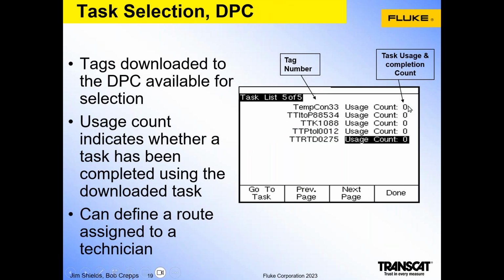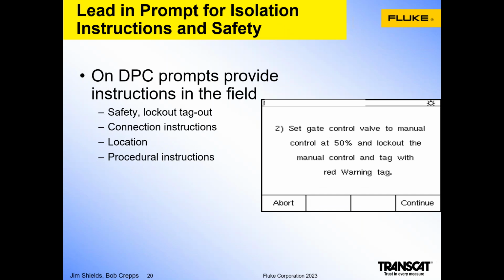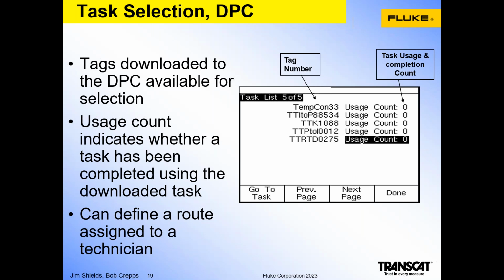When tags are downloaded to the Documenting Process Calibrator, there's a task list, and the task list has a usage count. This task list can be used as a punch list for the technician to know which tags he has calibrated and which tags he has not, based on usage count. When the calibration is performed and completed, the usage count changes from 0 to 1. And in an instance like this, it can constitute a route for the technician to go out and perform the calibration.